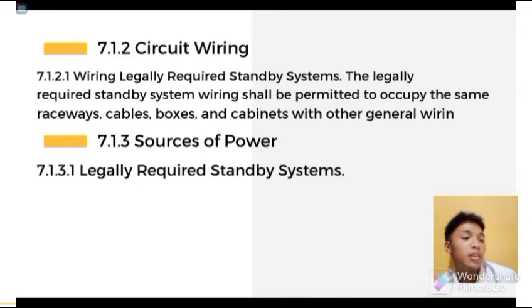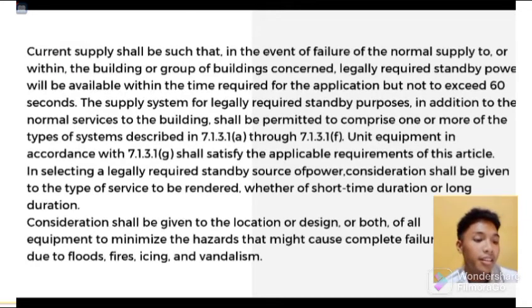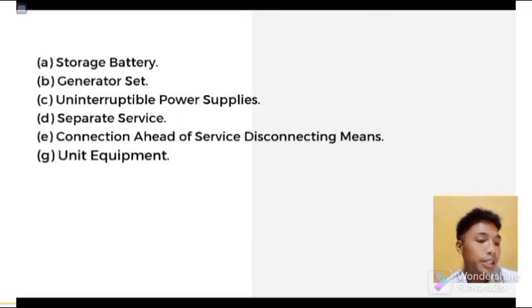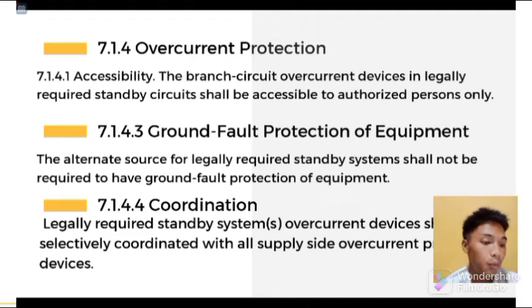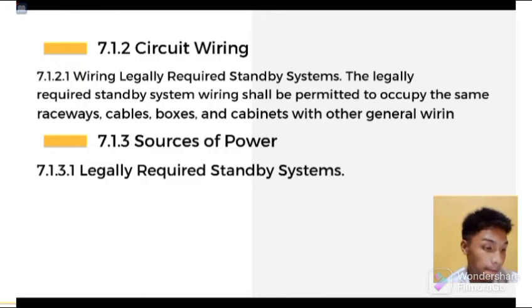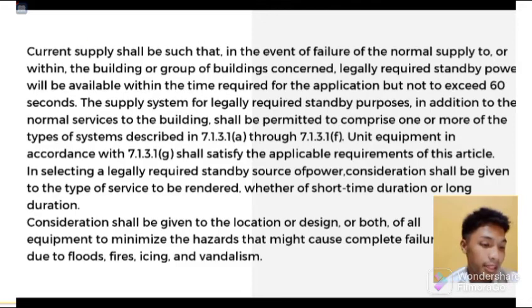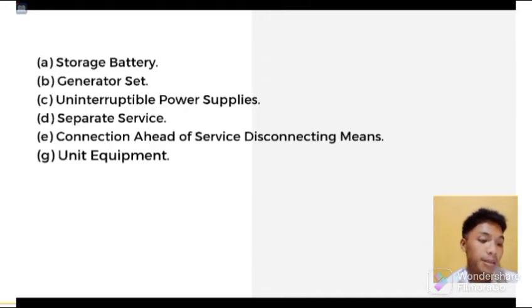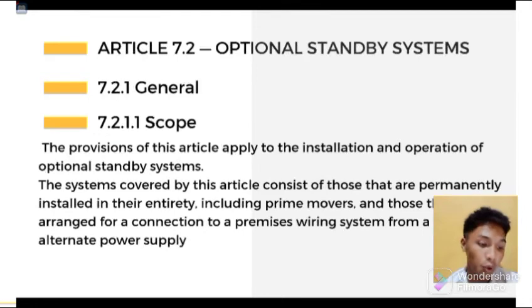Okay, so for our next article, Article 7.2, the optional standby system. We are done with the legally required standby system and now we are at optional standby systems. So we're in the scope. These rules apply to the installation and operation of optional standby systems, which include prime movers and those that are arranged for connection to a premises wiring system from a portable alternate power supply.